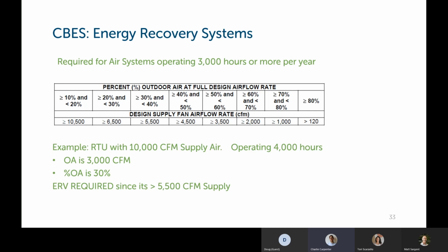and how I read through it. So the example I'll use is a rooftop unit, a pretty large one that has 10,000 CFM of supply air, and it's operating 4,000 hours per year. So based on that, it's over 3,000. So that means that you would need to then look at the table and the outdoor air part of the example is 3,000 CFM for this. So the percentage of outdoor air, which is the top level of the table for this unit, is 3,000 over 10,000. So that's 30%. So what you would do is go to the third column where it states greater than or equal to 30% and less than 40% outdoor air at design.